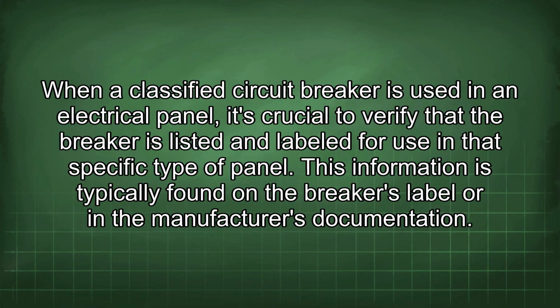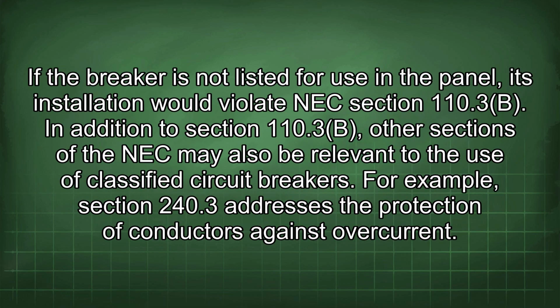When a classified circuit breaker is used in an electrical panel, it's crucial to verify that the breaker is listed and labeled for use in that specific type of panel. This information is typically found on the breaker's label or in the manufacturer's documentation. If the breaker is not listed for use in the panel, its installation would violate NEC Section 110.3(B).